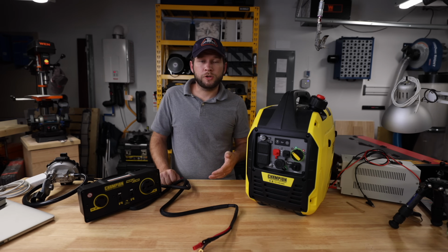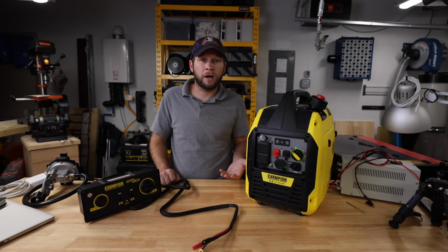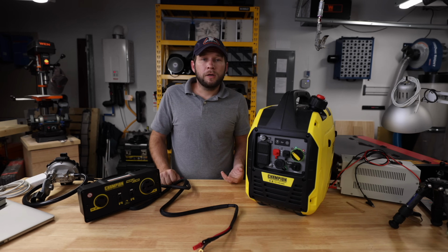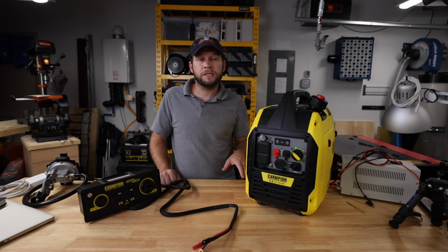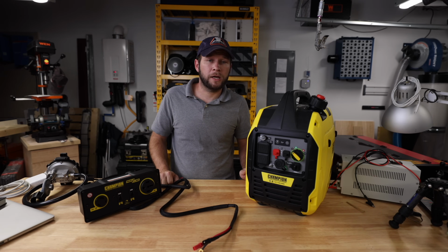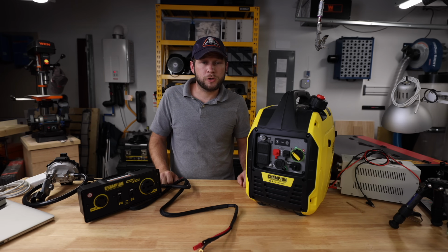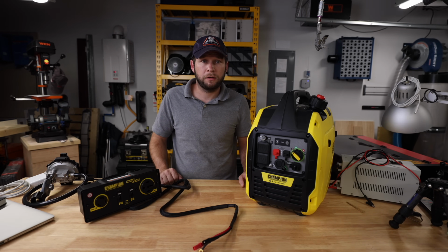Within reason, your 240 volt breakers, again, are not going to see 240 volts because they're not out of phase with each other. The problem comes in when you have a 120 volt circuit with a tandem breaker. This is done commonly with things like kitchen islands, where you may have two circuits going to the same place and they just run one wire with 3 conductors and a ground in it.